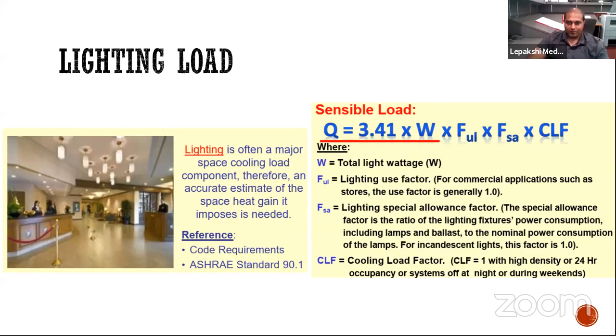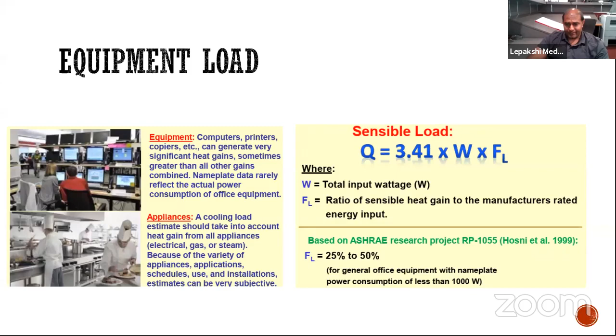For equipment, you'll have computers, printers, and so on. All these things generate heat, giving off some amount of heat into the space as instantaneous heat gain. You've got to account for that heat while doing your cooling load calculations. Those are the formulas you can use to come up with all this. You can get the information you need from the manufacturer's plate on the particular equipment, or from ASHRAE as well.